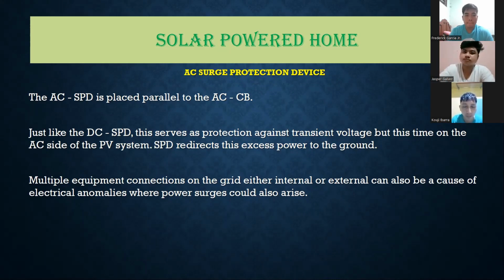Okay, so AC surge protection device. The AC SPD is placed parallel to the AC circuit breaker. Just like the DC SPD, this serves as protection against transient voltage, but this time on the AC side of the PV system. SPD redirects this excess power to the ground. Multiple equipment connections on the grid, either internal or external, can also be a cause of electrical anomalies where power surges could also arise. Okay, so thank you.